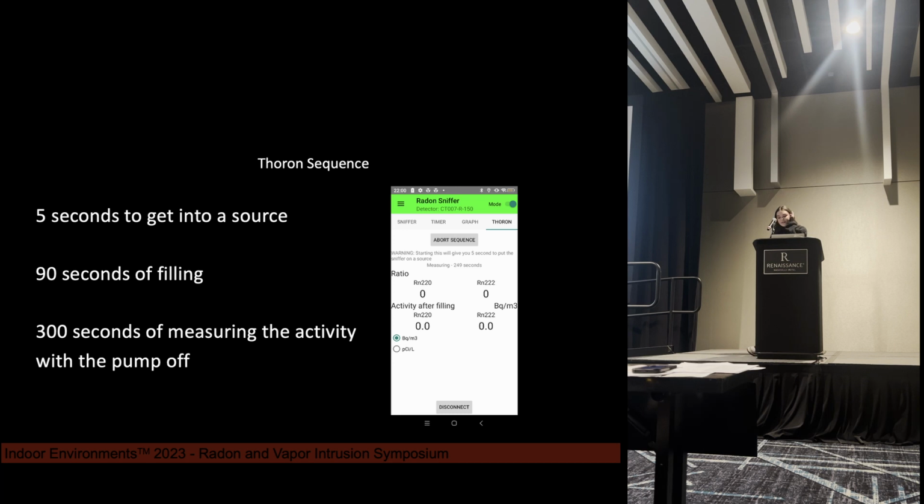Another issue is that the calculation assumes a clean cell. If there is radon progeny in the cell, the radon algorithm may not be accurate. The team at EIC are currently working on improving our thoron module, but that's as far as we have it so far, so now we can move on to radon in water screening.